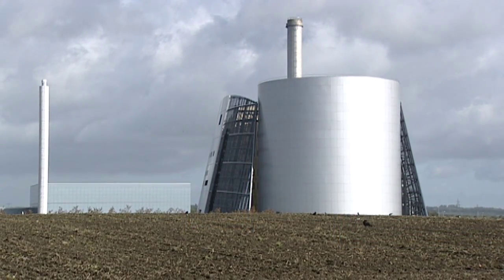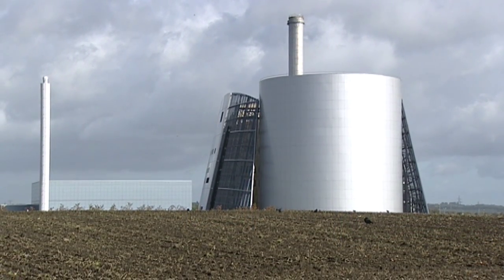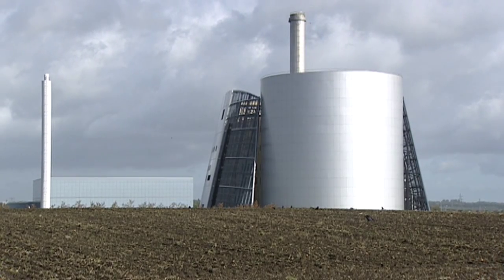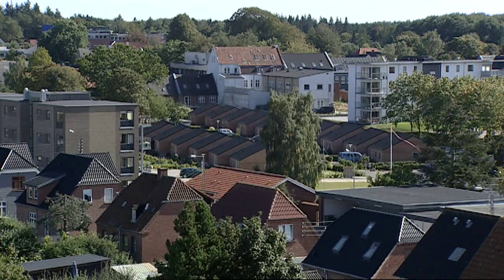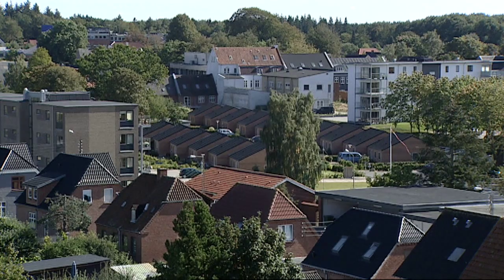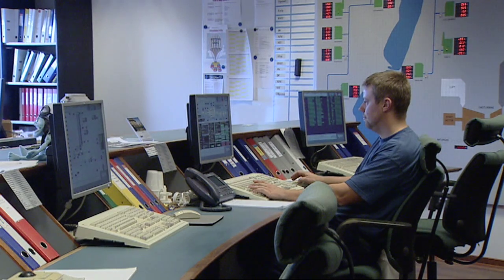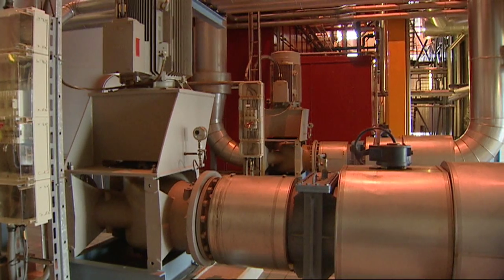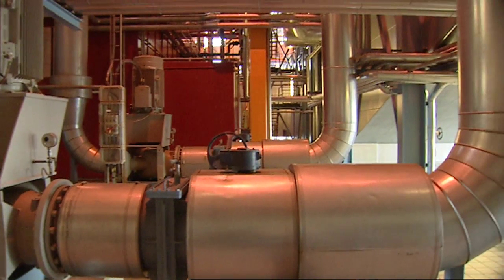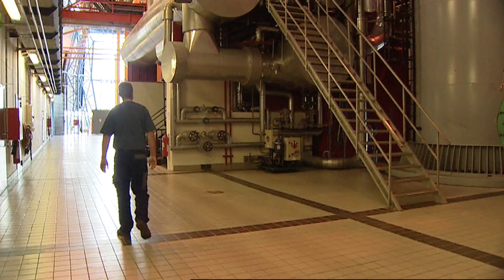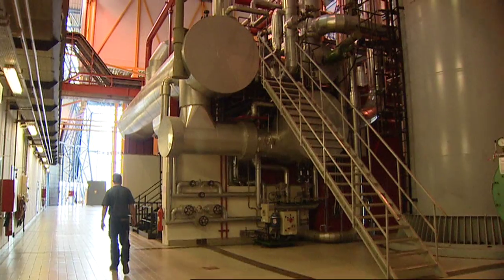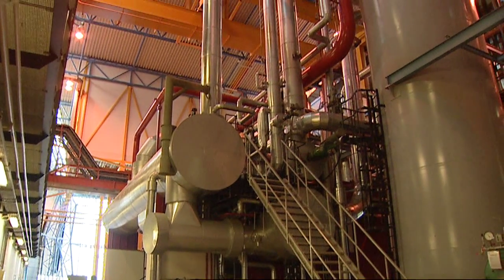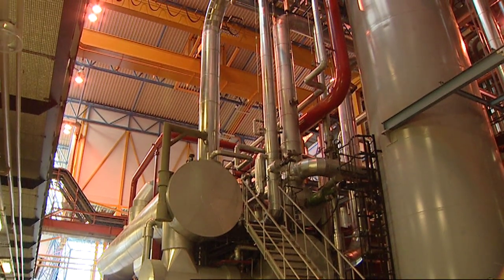The use of holding tanks allows the facility to produce heat periodically, establishing an energy reserve sufficient to heat the community for up to several days without the facility having to heat water constantly. This allows the facility to shut down heat generation at night or during weekends, or when running the boilers would be uneconomic due to low demand or fluctuating fuel costs.